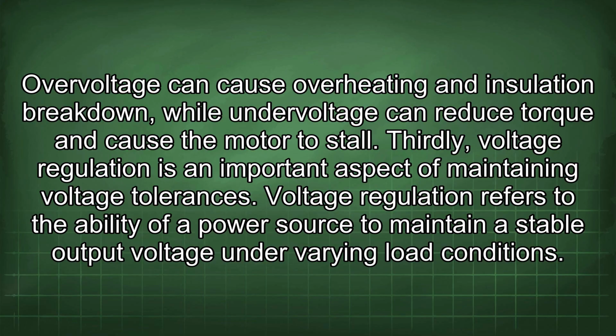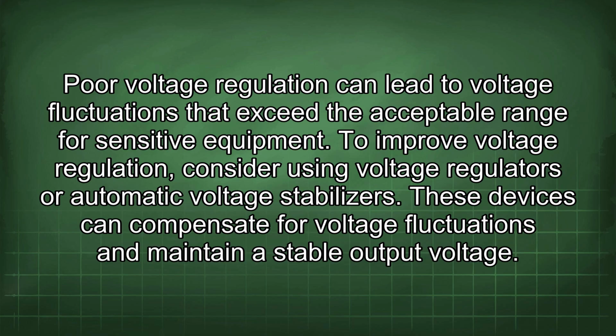Thirdly, voltage regulation is an important aspect of maintaining voltage tolerances. Voltage regulation refers to the ability of a power source to maintain a stable output voltage under varying load conditions. Poor voltage regulation can lead to voltage fluctuations that exceed the acceptable range for sensitive equipment. To improve voltage regulation, consider using voltage regulators or automatic voltage stabilizers. These devices can compensate for voltage fluctuations and maintain a stable output voltage.